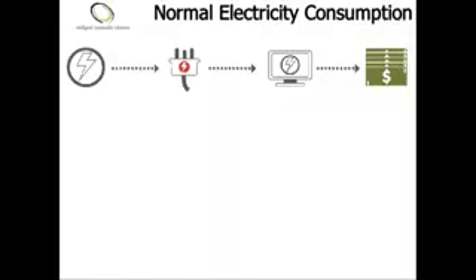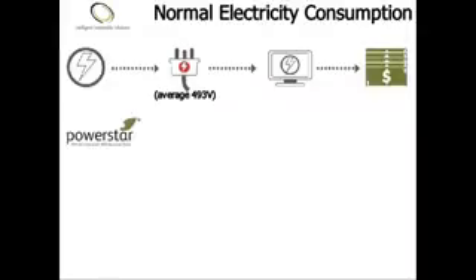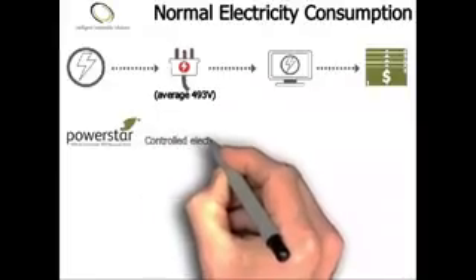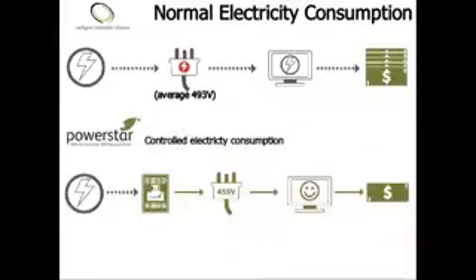The next slide shows normal electricity consumption. We have the power supplied from the grid. The average voltage in the USA has been measured at 493 volts. This elevated voltage can cause failure in electrical equipment and shorten lifetime. Operating at this increased voltage costs more to operate equipment, and therefore we consume more energy than necessary.